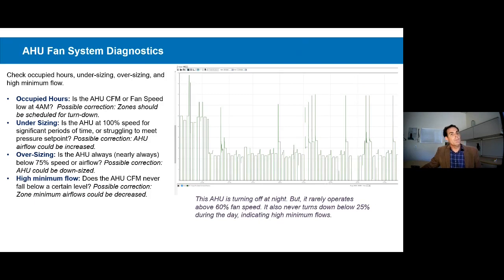For fan systems, the list of diagnostics that you see on this slide are pretty much the same. So again, we'll want to do the 4 a.m. and 4 p.m. test. In this graphic, you can see that that's happening quite well for this air handler. Every air handler that we have should be at a reduced state at 4 o'clock in the morning. That's frequently not the case in our hospitals, but that's something we want to note during design. And then we also want to look at the actual fan speed, right? This fan speed never gets above 75% in this slide, and it spends a huge block of time down at 25% fan speed.